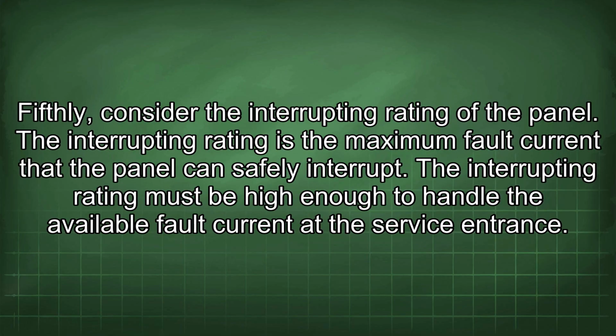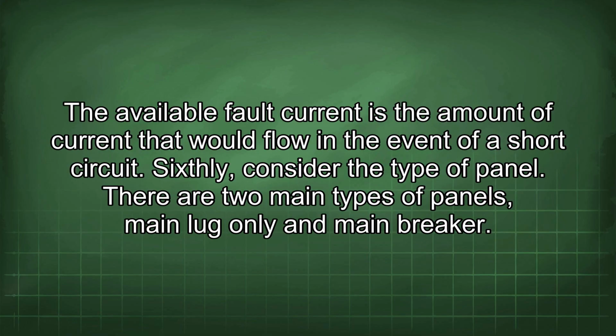Fifthly, consider the interrupting rating of the panel. The interrupting rating is the maximum fault current that the panel can safely interrupt. The interrupting rating must be high enough to handle the available fault current at the service entrance. The available fault current is the amount of current that would flow in the event of a short circuit.